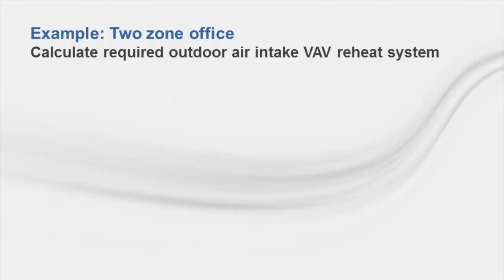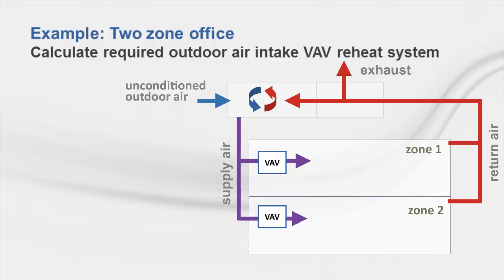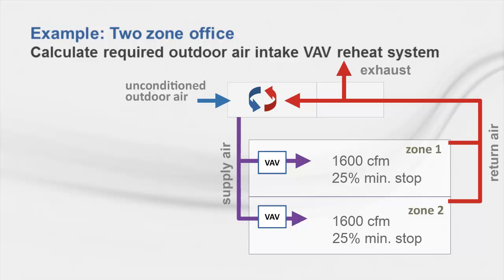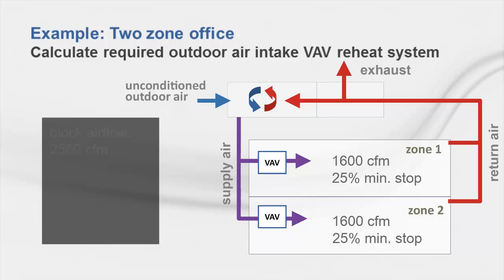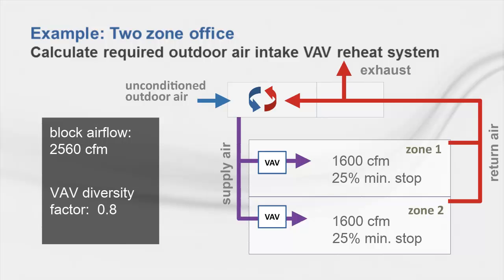To describe the multi-zone calculation process, I'm going to walk you through a simple example and show you how TRACE solves for the outdoor air intake. For this example, let's solve for outdoor air intake for a two-zone VAV system in an office building. The design peak air flow for each zone is 1,600 CFM with a 25% minimum stop, and the system block air flow is 2,560 CFM, which equates to a system diversity factor of 0.8.